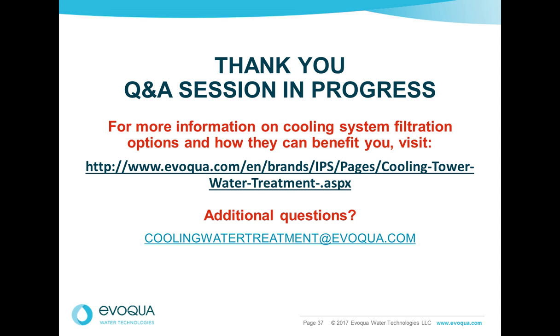So yes, absolutely. Chlorine, like Bob said, is a great tool. Bromine is another good option, and probably a better option in many cases for controlling bacteria. But it's one of those cases where too much of a good thing is not a good thing. Overfeeding oxidizing biocide is going to cause corrosion. No two ways about it. For the most part, the chloride that causes the corrosion is coming in with the makeup water and concentrating up. It's not from the chlorine you're feeding, unless you're feeding way too much chlorine. Yep. I've seen it where people just turn up the pumps and start cranking it up, and all of a sudden they've got leaks. So be careful of that. Work with your water treater.